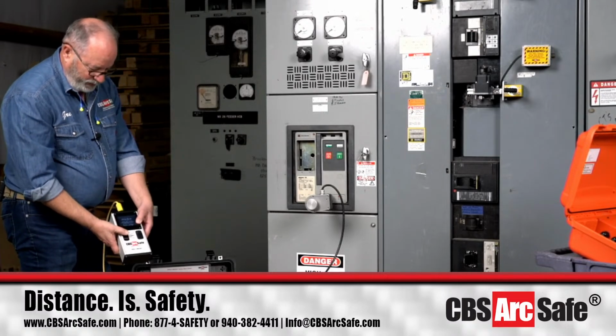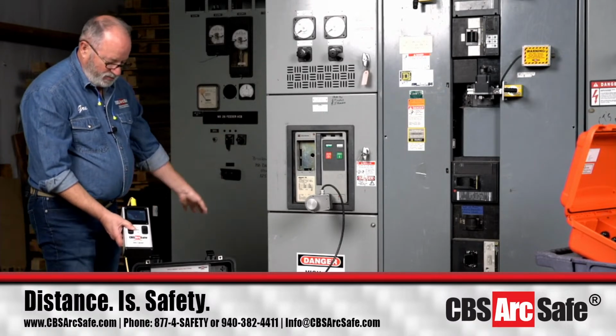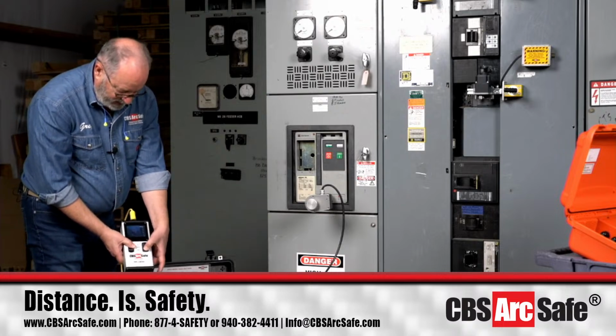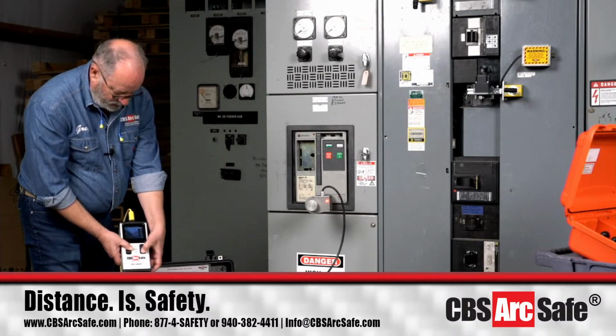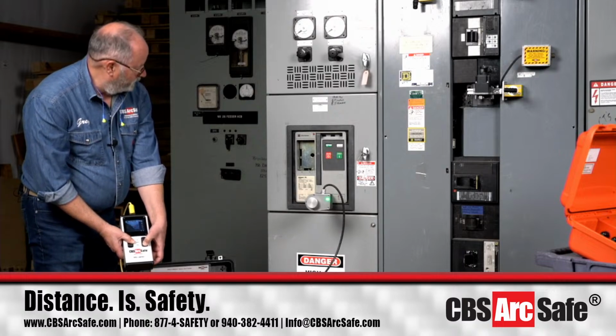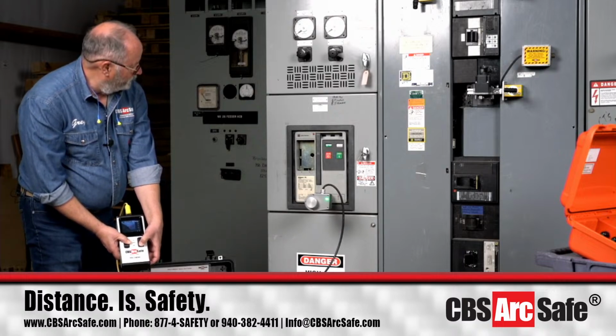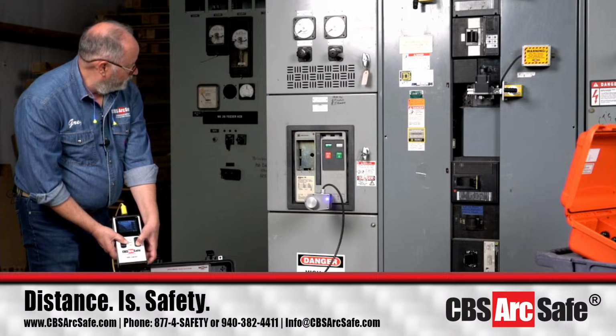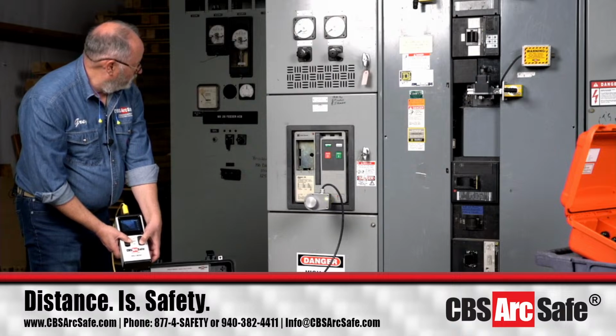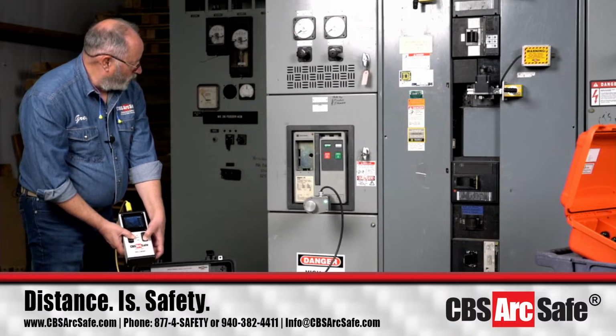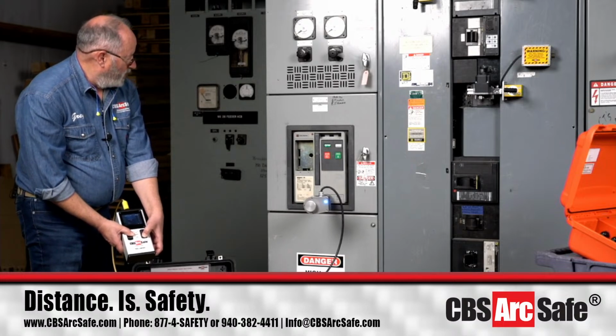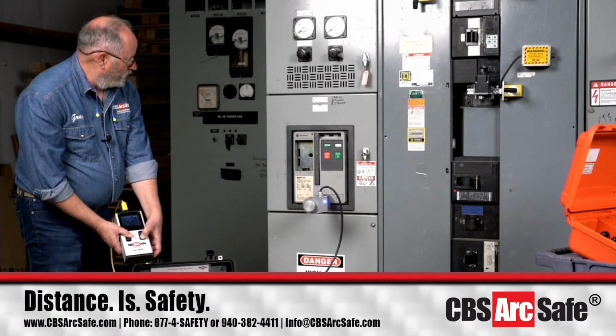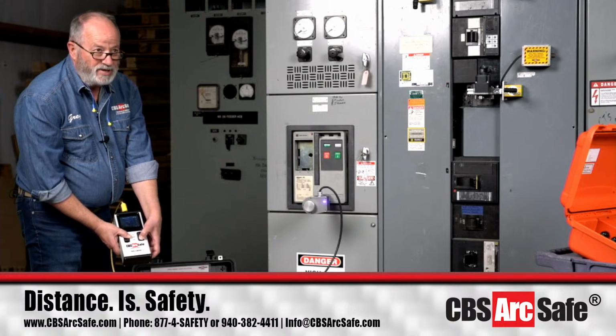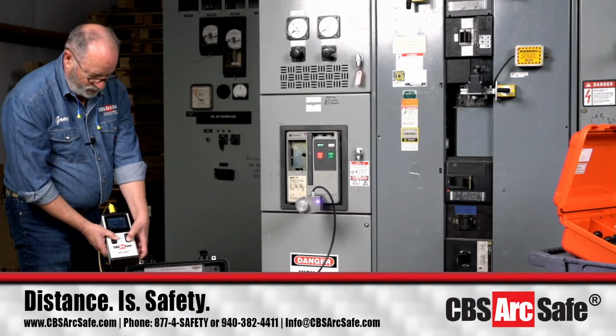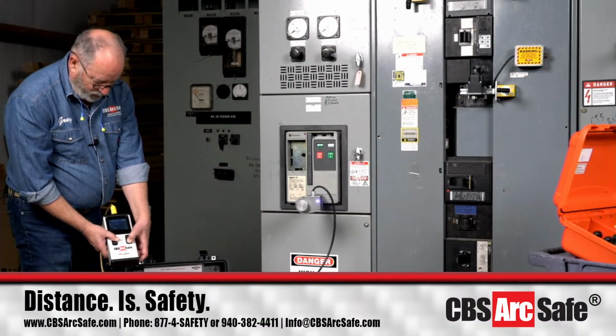We go to enable, and because the breaker's in the in position, we hold the out position down. This works on the mains and the feeders, and it's going to rack the breaker. I think it's about 38 turns on the racking mechanism to go in and out, and this will handle all the big breakers too.